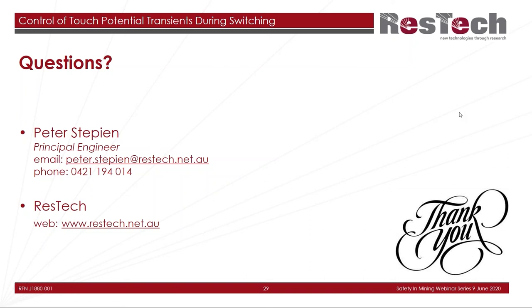So the next question from Mars is, without the knowledge to verify your simulation, not knowing the voltage on the secondary of the transformer, and it may be a different topic, will there be an increase in total voltage higher than the cable rating, say for 0.6/1 kV can be subjected to 1.2 kV phase to phase or 0.7 kV phase to earth? That's right. Yeah, that's correct, Mars.